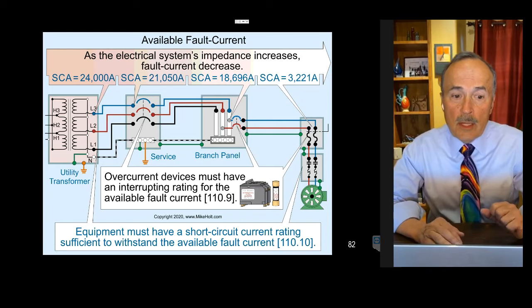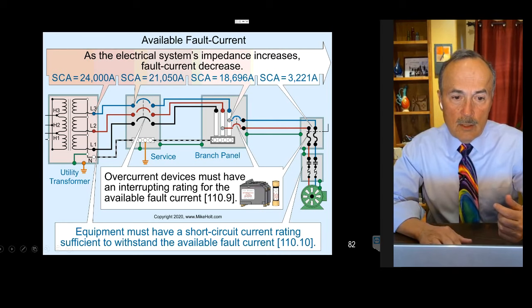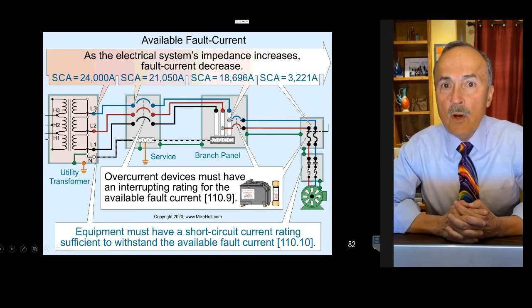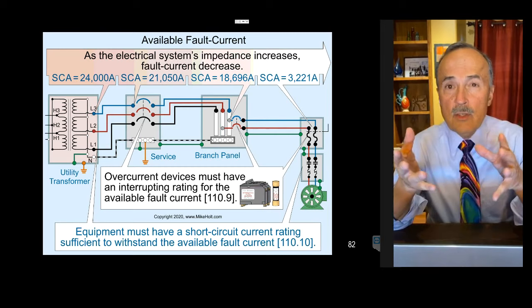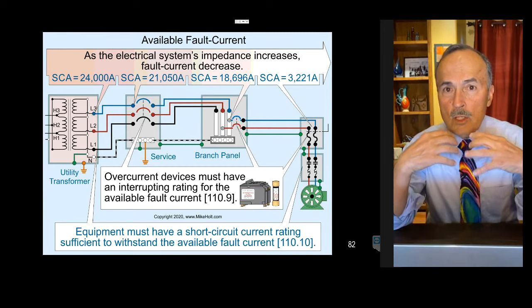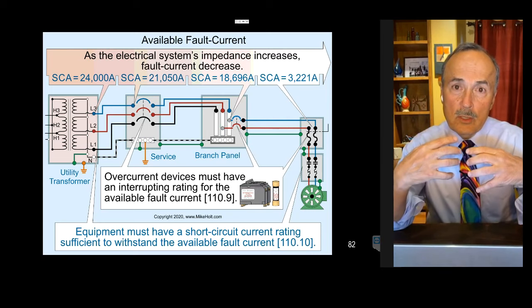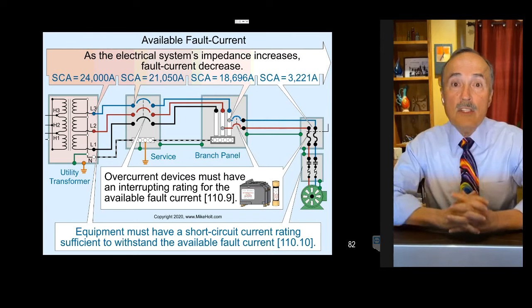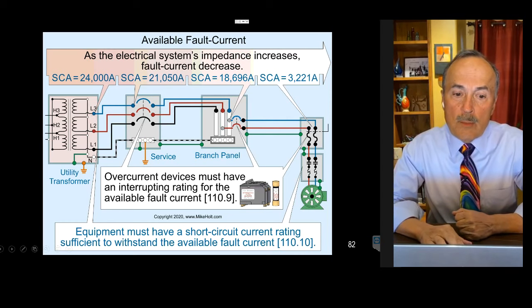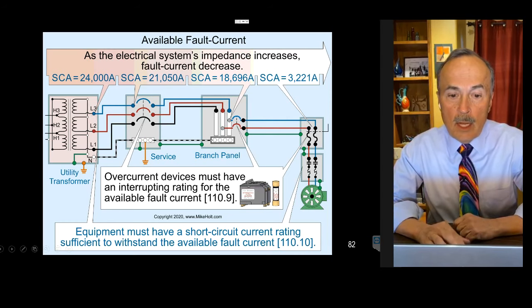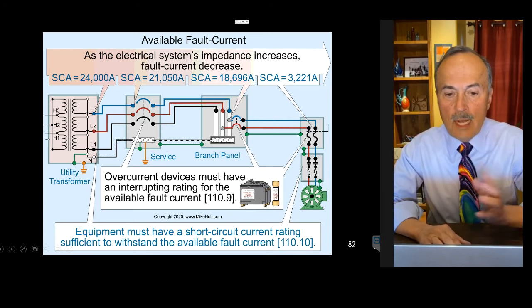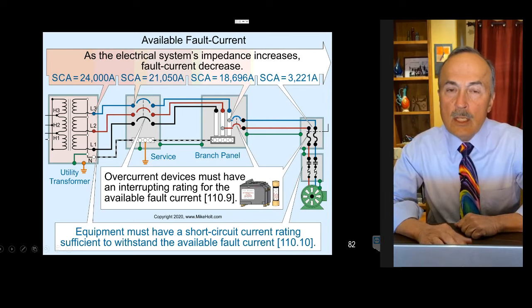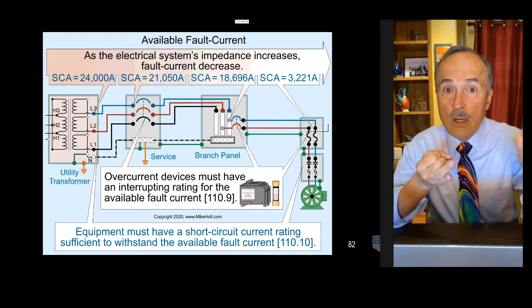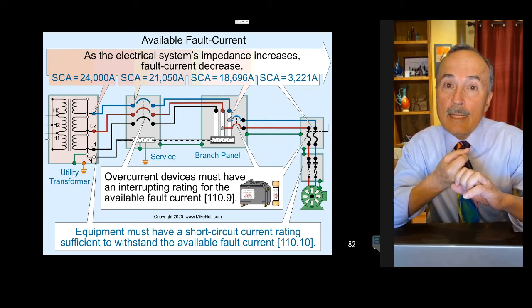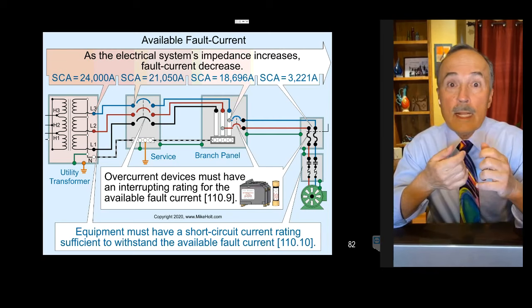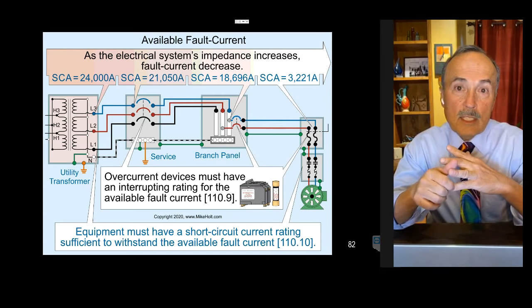The available fault of a power supply is going to be limited on the output to the input available fault, the impedance of the transformer, the voltage of the transformer, and the kVA of the transformer. So an example here, this is showing that it's 24,000 amperes available fault. Now you can contact the utility, give them an address, say, hey, listen, I have this address. What's the available fault at that transformer? So now we're talking about if there was a fault, there's 24,000 amperes of available fault, and you better make sure that the equipment you have is rated for that 24,000 amperes. However, you are going to be running conductors between the transformer and the premises. Let's say this disconnecting means, okay? Probably should show, well, we're not going to show a meter here because we're just going to show a disconnecting means. Because the conductor has impedance, it has reactance, all covered in theory.